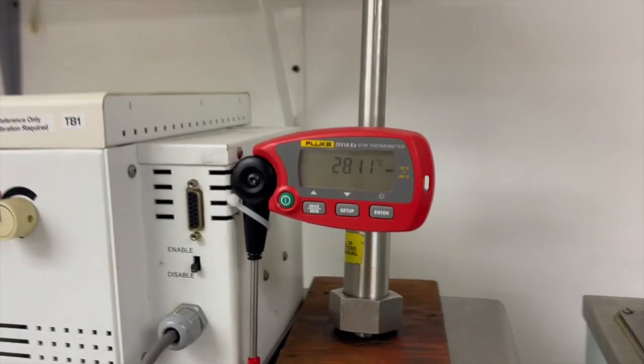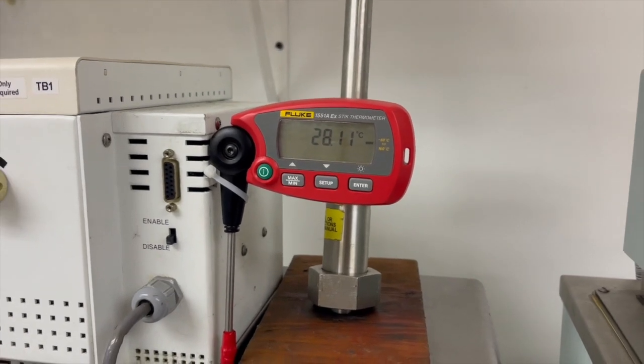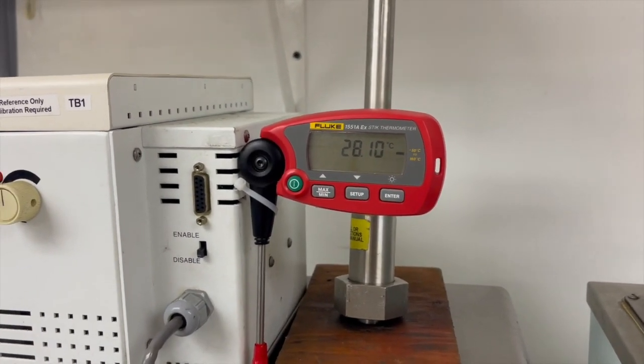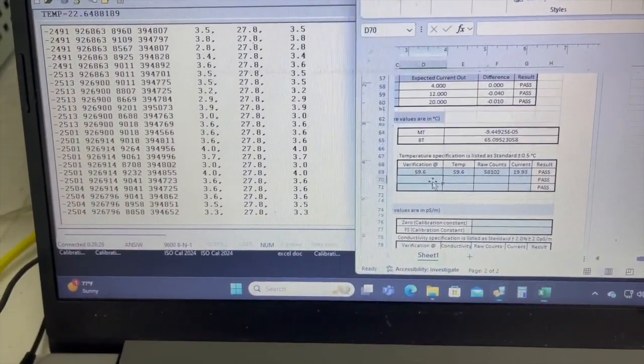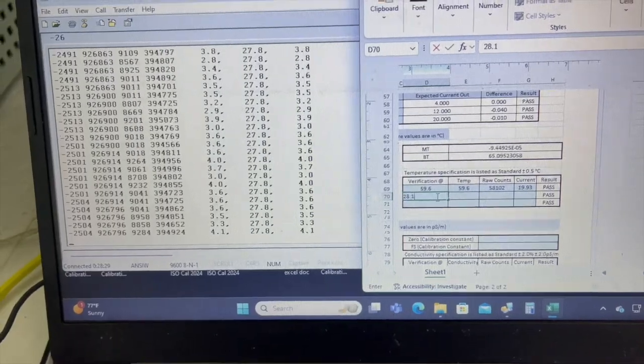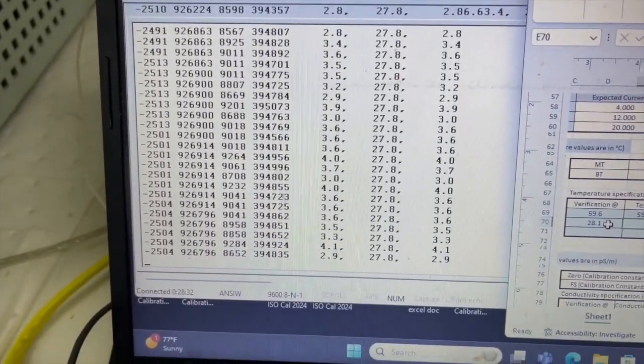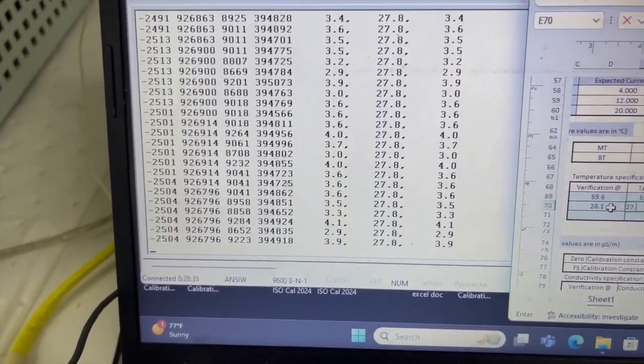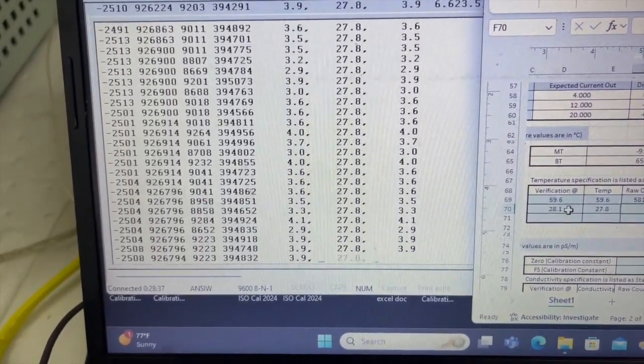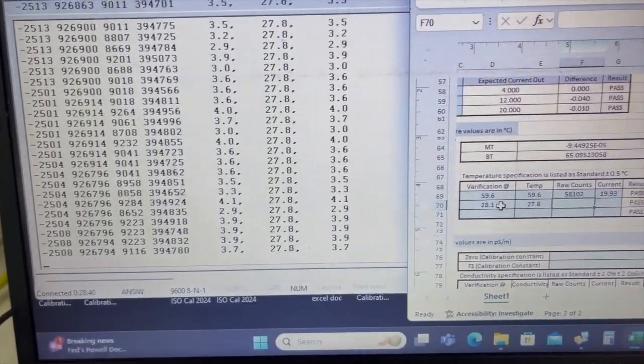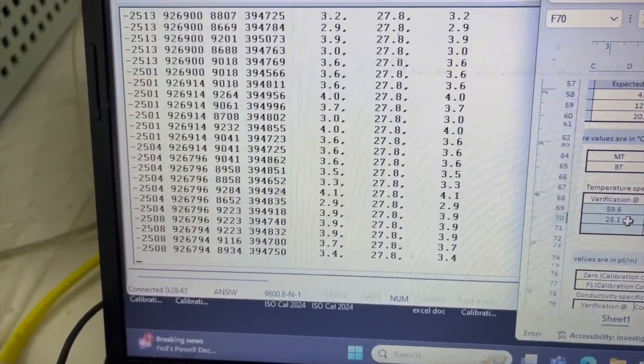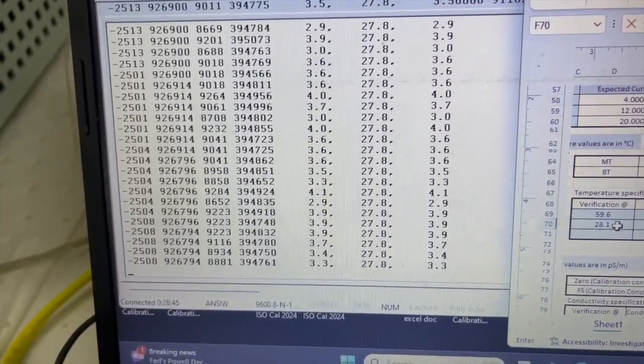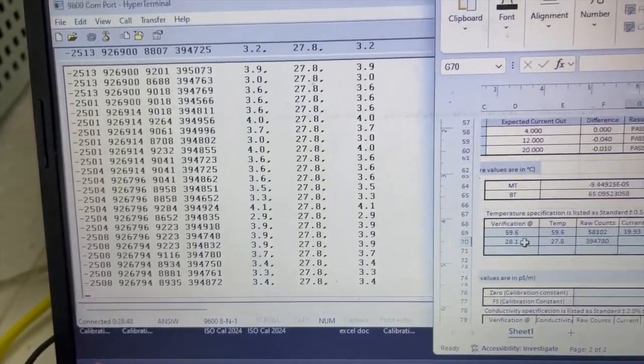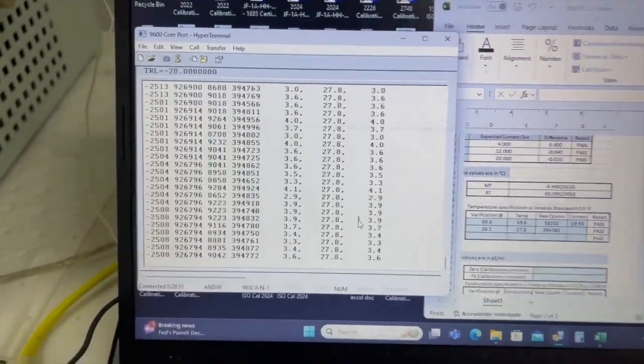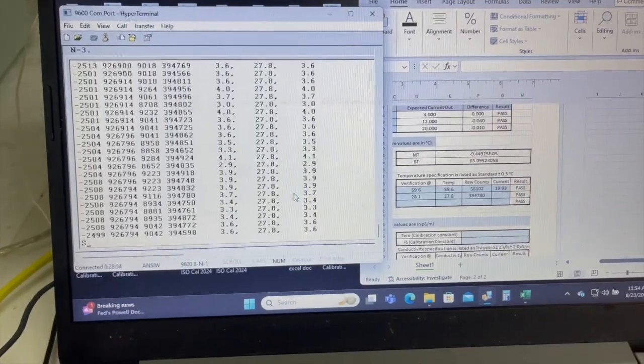So now that the sensor has soaked for 30 minutes at the middle temperature, we check the temperature probe, we get a 28.1. So we'll go over here and we'll enter 28.1. And our sensor is reading 27.8, which is within the plus or minus 0.5 standard deviation. We have a temperature count of 394,780, which is good.